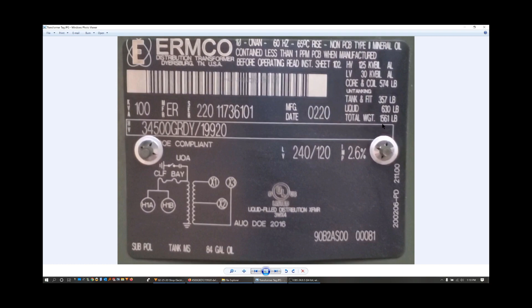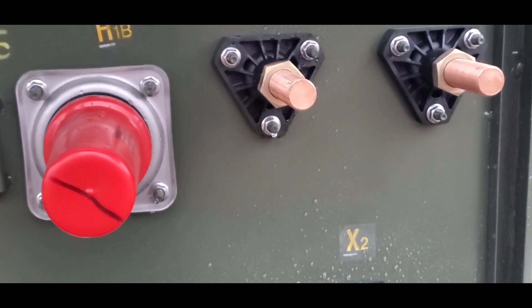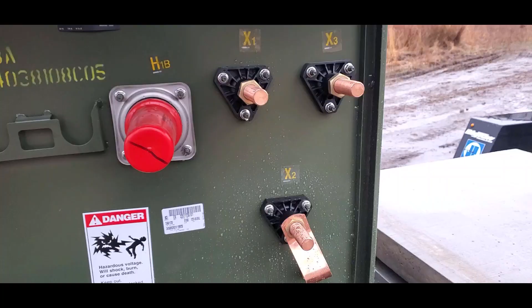So it's a monster. There's the amount of oil it has in it, 84 gallons of oil, and it's like 650 pounds. So 630 pounds of liquid. The tank is 350. Core and the coil 574. So this thing weighs in at 1,560 pounds. It's a monster. There's some big lugs.